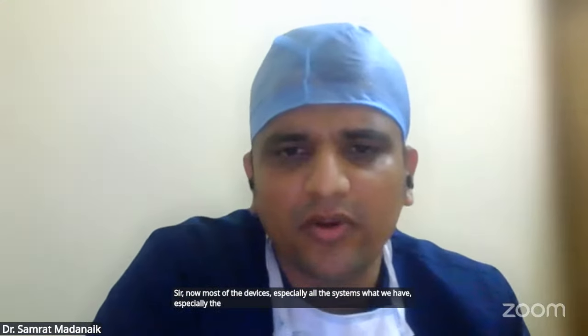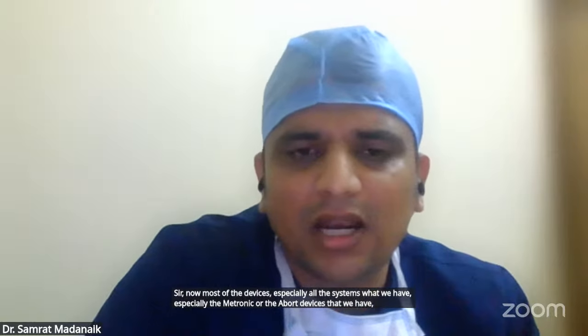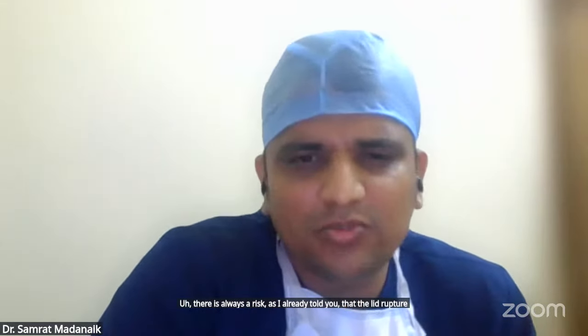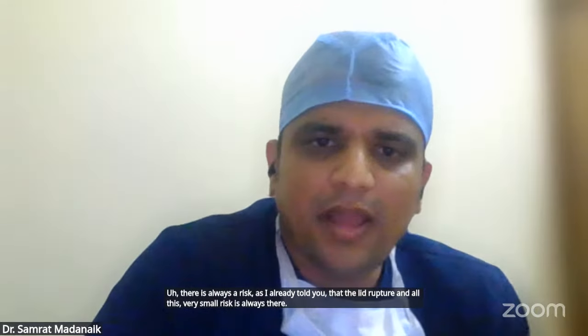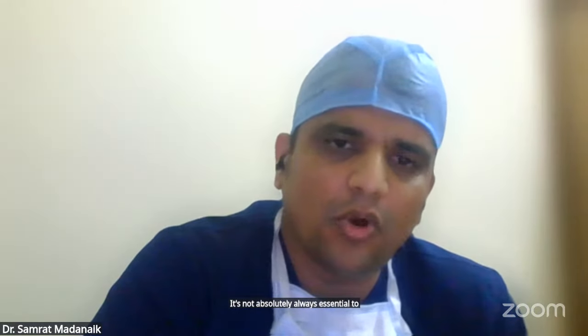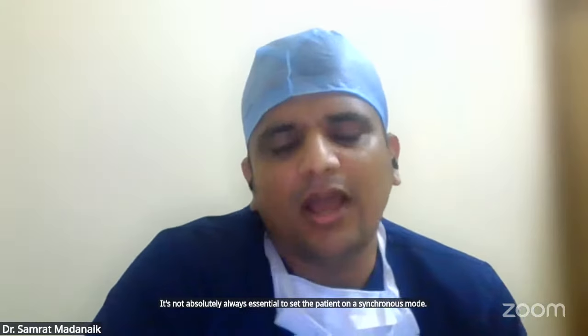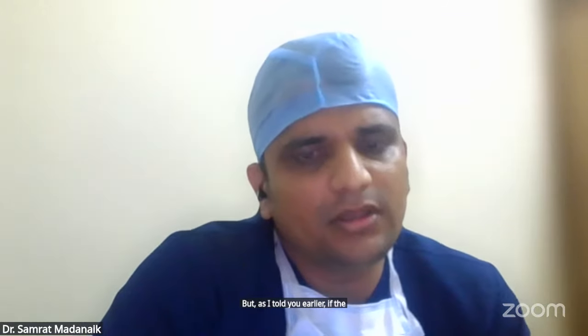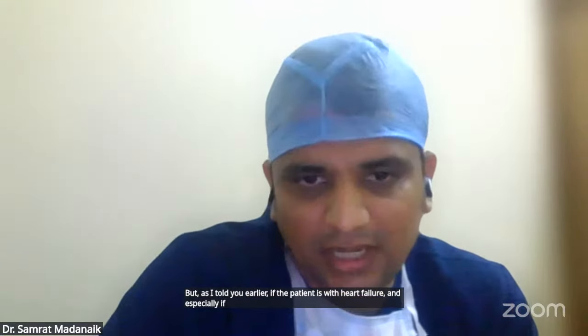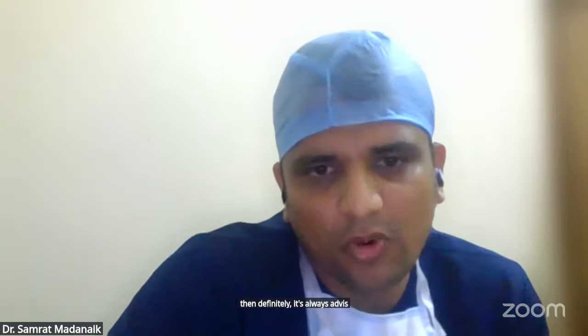Sir, most of the devices, especially the Medtronic or Abbott devices that we have, are recommended as MRI compatible. There is always a very small risk, as I already told you, of lead rupture. It's not absolutely essential to set the patient on asynchronous mode. But as I told you earlier, if the patient has heart failure, and especially is pacing dependent, and your MRI machine is of the older generation, then definitely it's advisable to reprogram these devices.